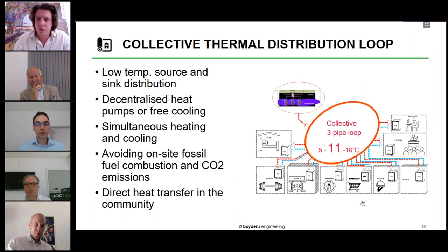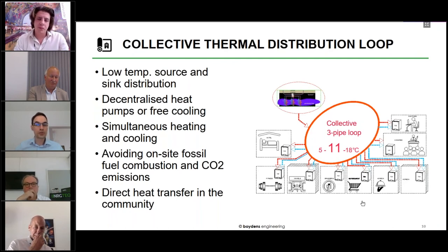Now, about that collective thermal distribution loop, we have a three-pipe system. So we have one main distribution pipe, which is supplying temperature at around 11 degrees Celsius to the decentralized heat pumps. And this water can either be used by the heat pumps to produce cold water, and then the return temperature will be 18 degrees, or to produce hot water on the secondary side, and then the return temperature will be around 5 degrees. With the water at 11 degrees, it can also be used for free cooling if the temperature is low enough for the secondary systems.